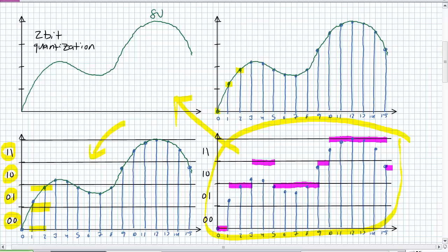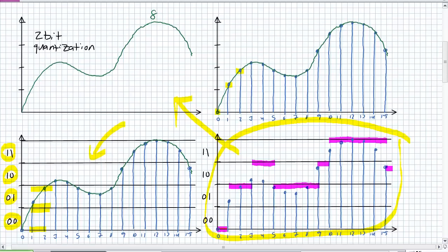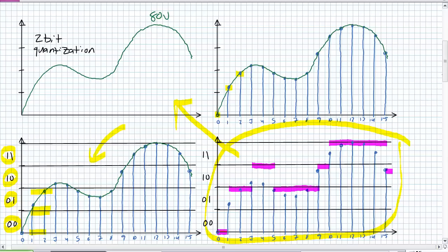Let's say, for example, this is maxing out at like 8 volts, 8 volt maximum is represented by 1, 1. Whereas this could also be an 80 volts maximum, where 80 volts is represented as 1, 1. It's still kind of the same shape of waveform. And it's still doing the same sampling. And it's still doing the same quantization. But realize 1, 1 represents 80 volts, whereas our previous example, 1, 1 represents 8 volts. So that concept of range and granularity when you're setting up these things. And your expected values know what to expect.